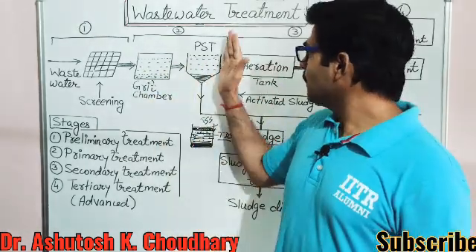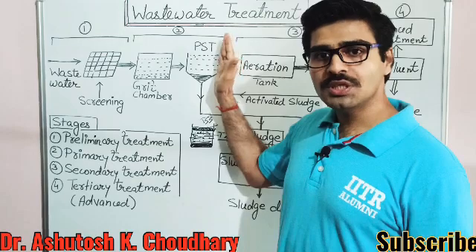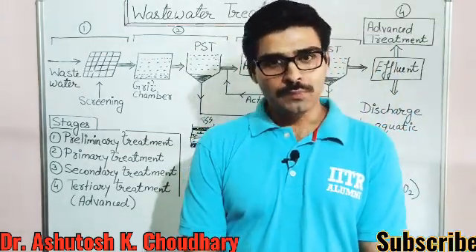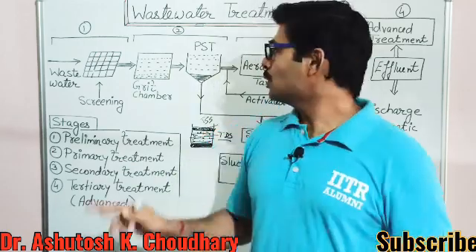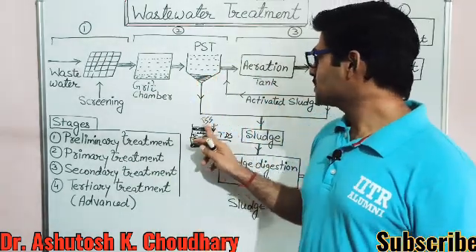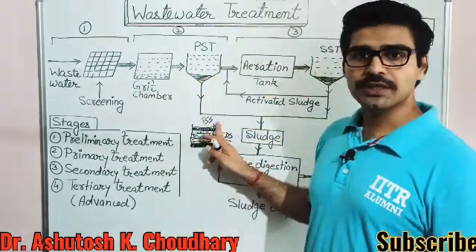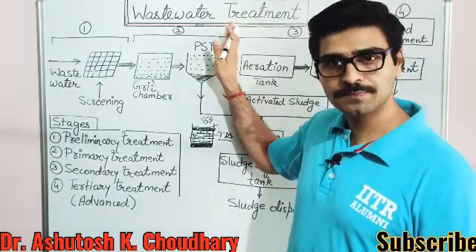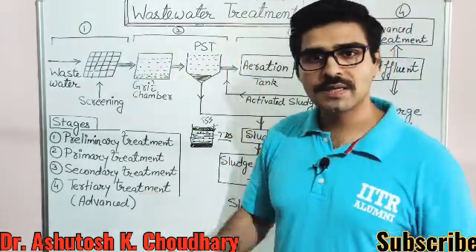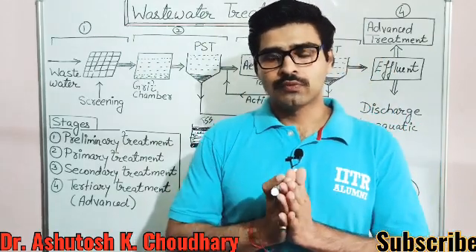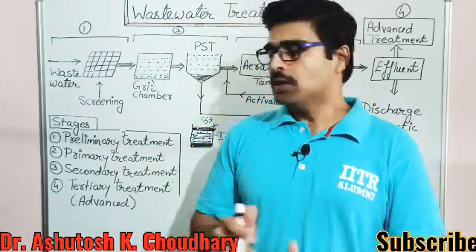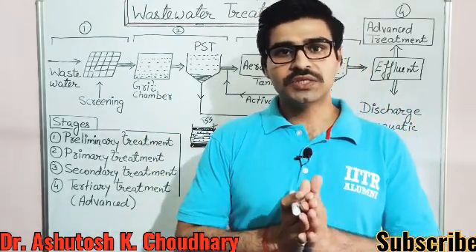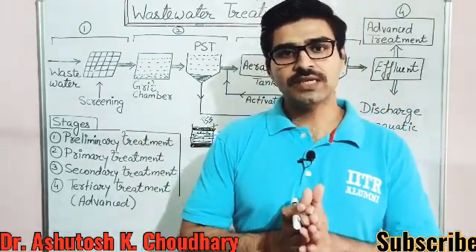Up to this stage there is 30 to 40 percent removal of BOD and about 60 percent removal of suspended solids. However, this removal is not sufficient to meet discharge limits, so the water is not yet fully treated.